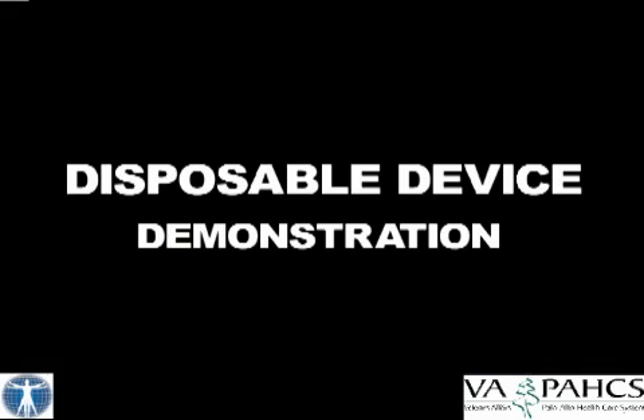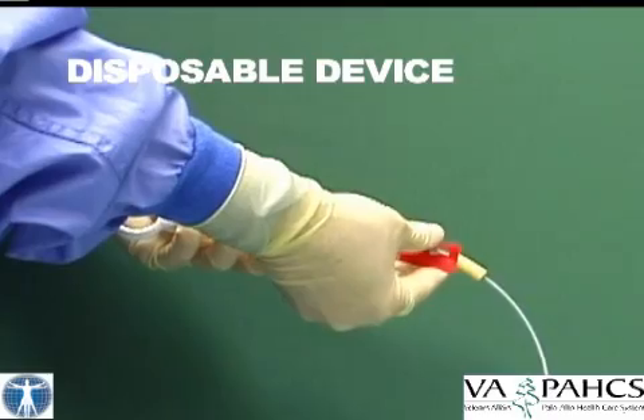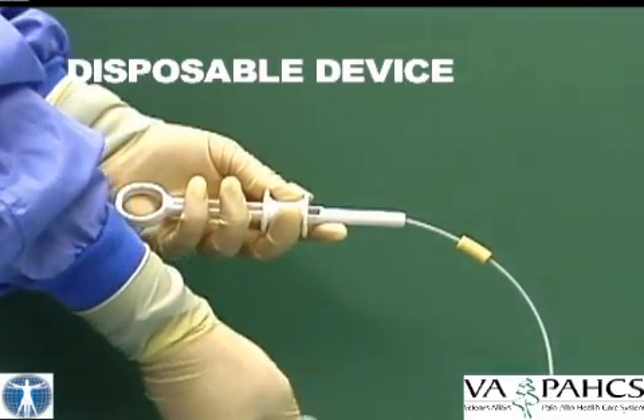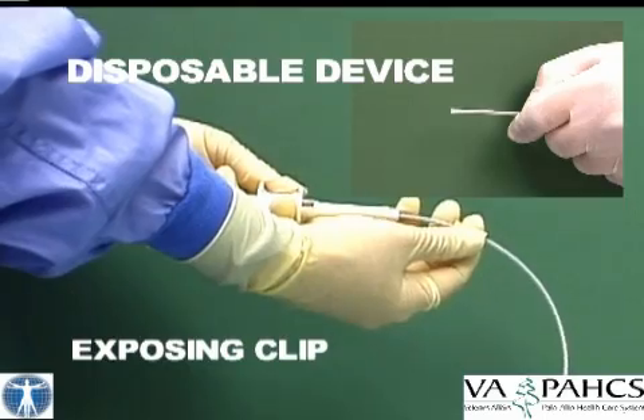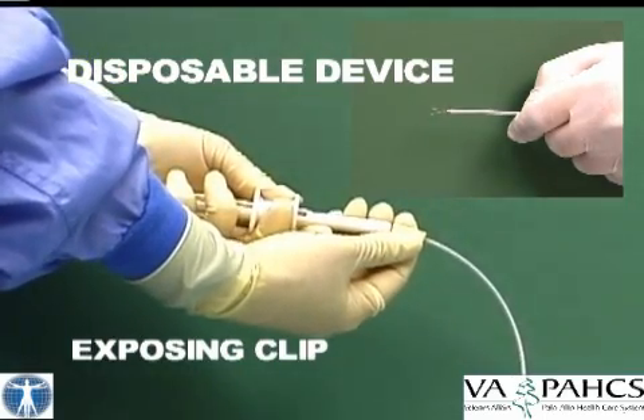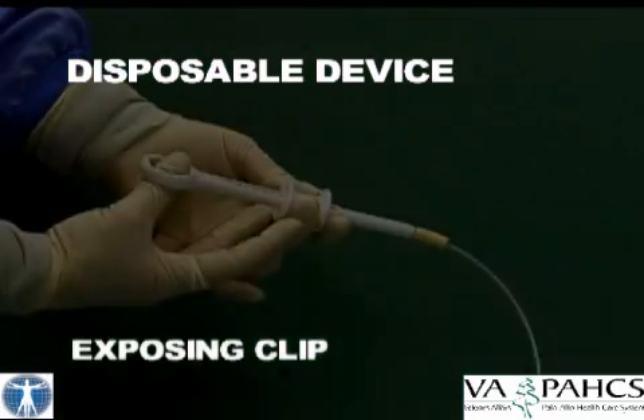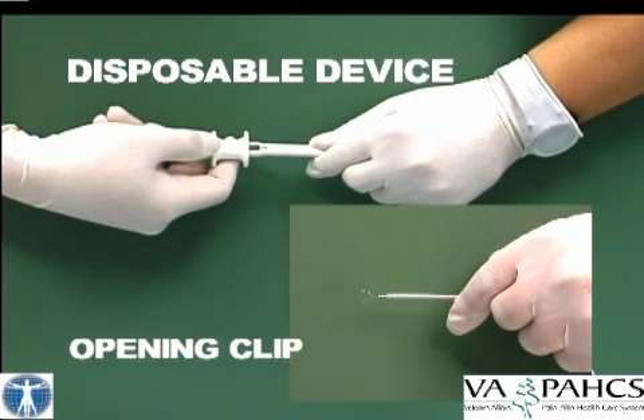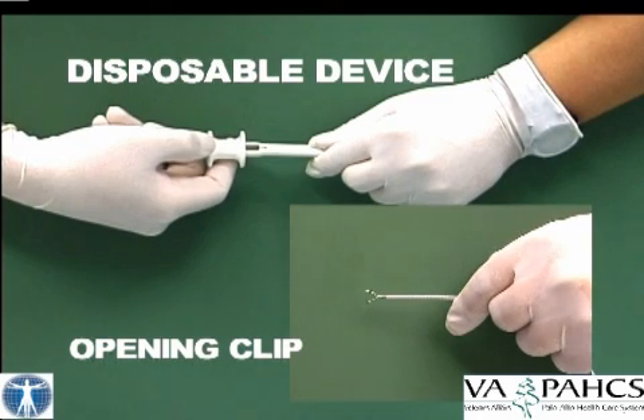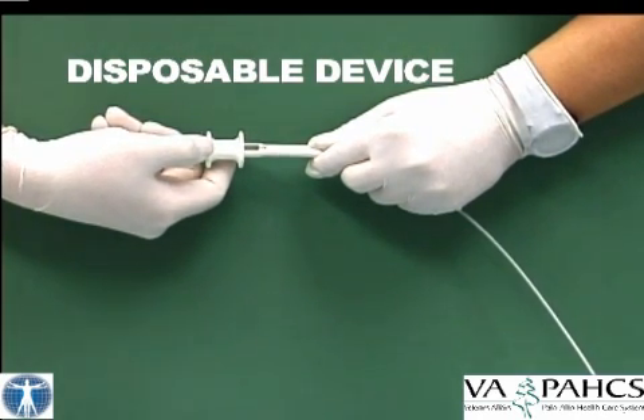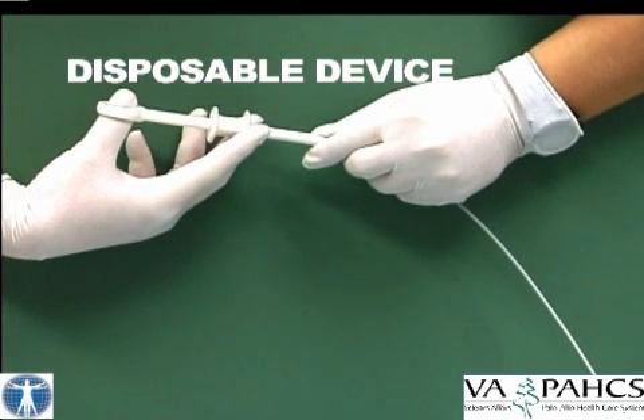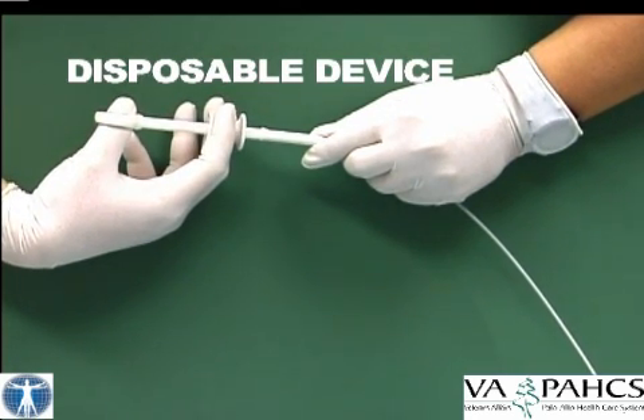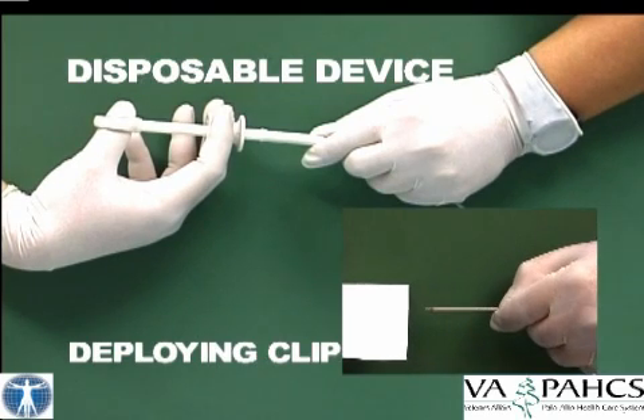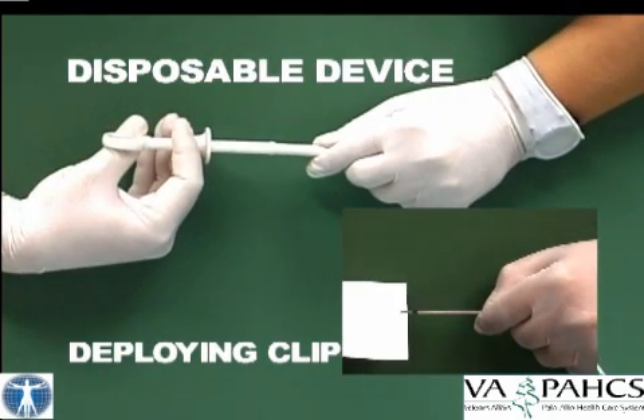We will now demonstrate the single-use disposable device. The device comes ready to load into the endoscope working channel. Once the tip of the device is exposed from the endoscope, remove the red plastic tab. Next, slide the yellow plastic piece toward the handle to expose the clip. The clip prongs are maximally opened by pulling the slider toward the handle ring. Again, you must be careful not to move the slider too far and prematurely deploy the clip. To deploy the clip, pull the slider toward the handle ring until the prongs are closed and the clip is released. The disposable clip applicator cannot be reused.